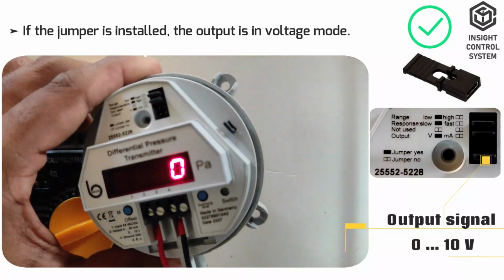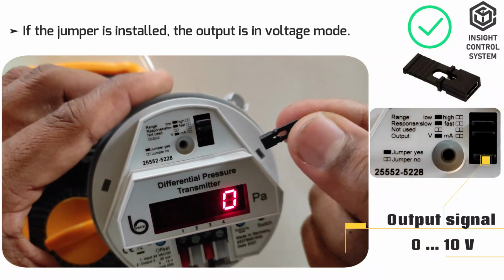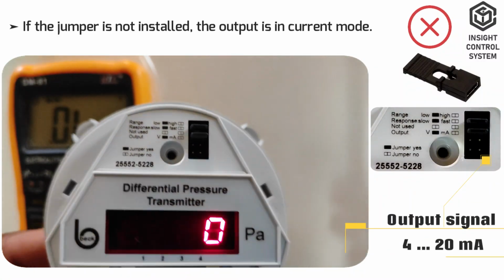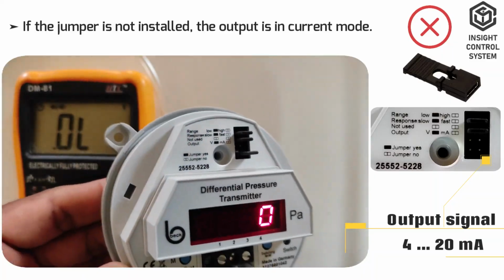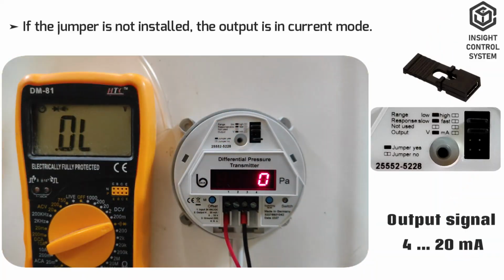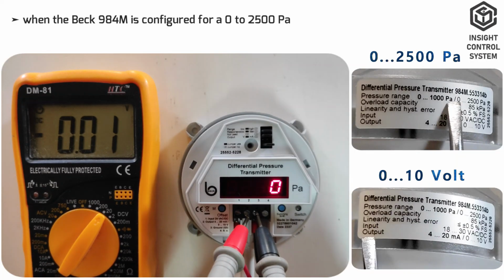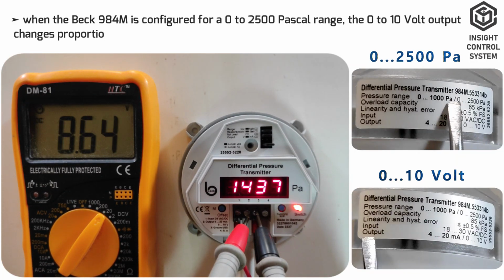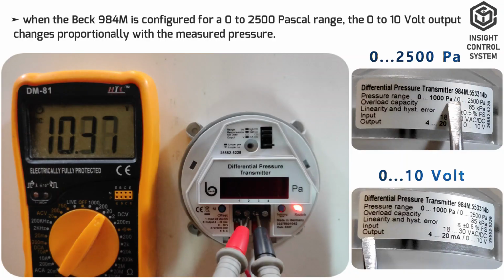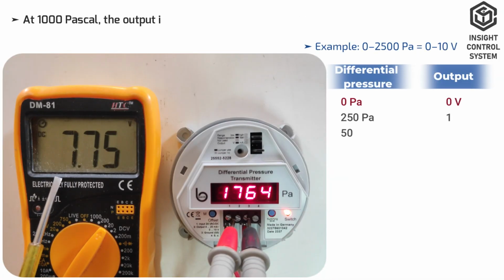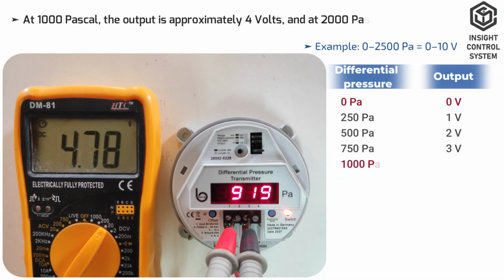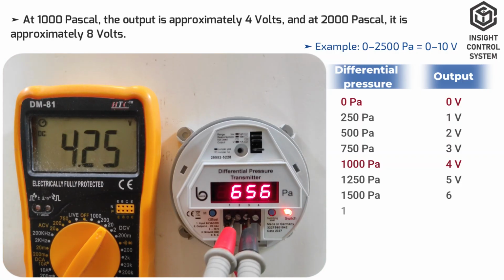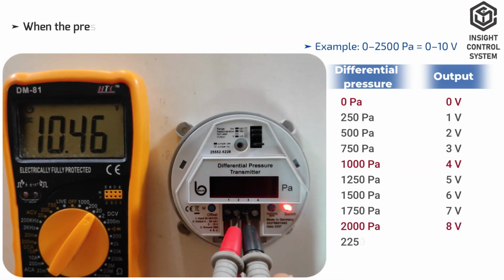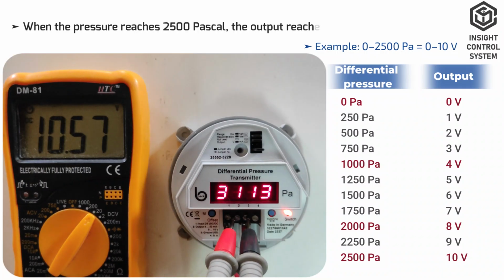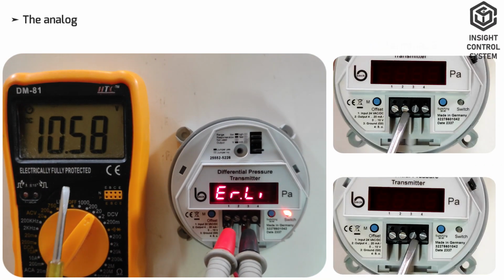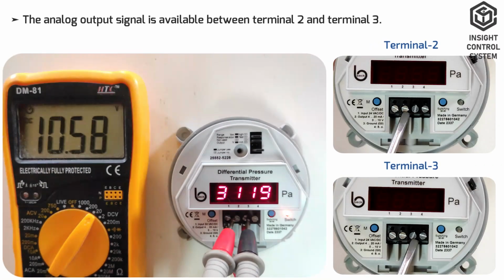If the jumper is installed, the output is in voltage mode. If the jumper is not installed, the output is in current mode. When the Beck 984M is configured for a 0 to 2500 Pascal range, the 0 to 10 volt output changes proportionally with the measured pressure. At 1000 Pascal, the output is approximately 4 volts, and at 2000 Pascal, it is approximately 8 volts. When the pressure reaches 2500 Pascal, the output reaches 10 volts. The analog output signal is available between terminals 2 and 3.